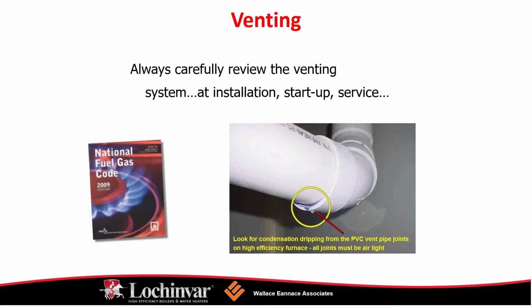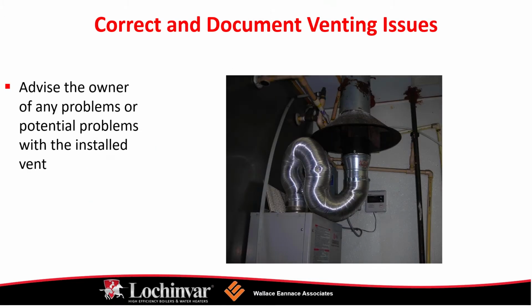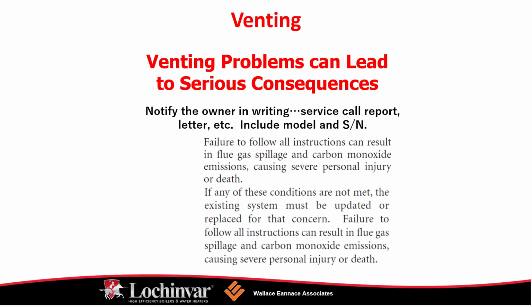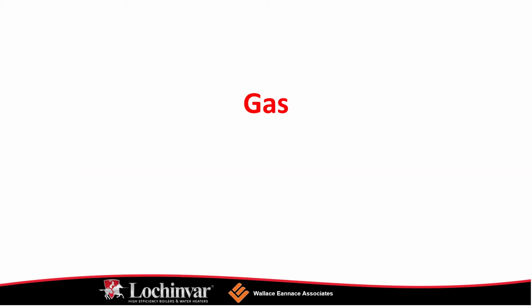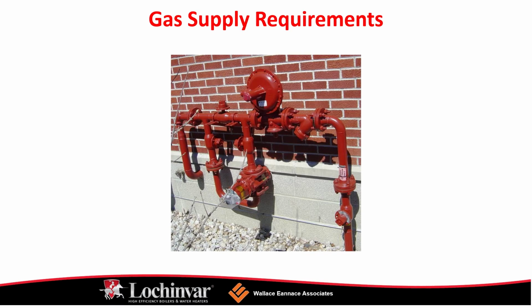Again, sidewall venting can be a problem depending on local codes, but here's a snapshot of maybe not a good location. There's another snapshot of maybe not a good location. These pictures are silly, but these are real life photos. This stuff happens. I've run into a lot of problems in the field where someone thinks it's the boiler itself and it's simply an error due to venting. So venting's critical, and you want to rely on us as the rep for Lochinvar to help you through that phase of the job if required. We're happy to do that for you.